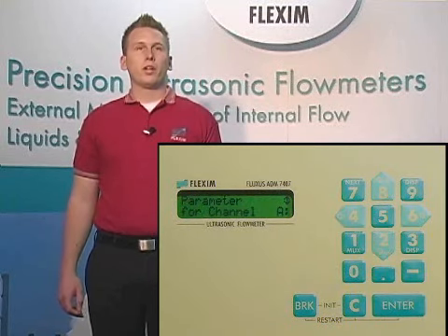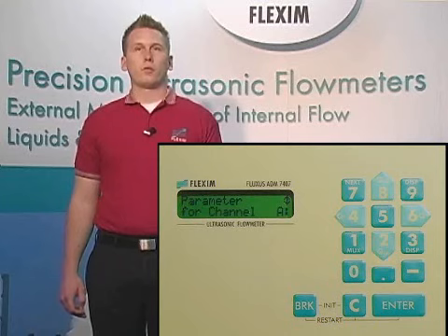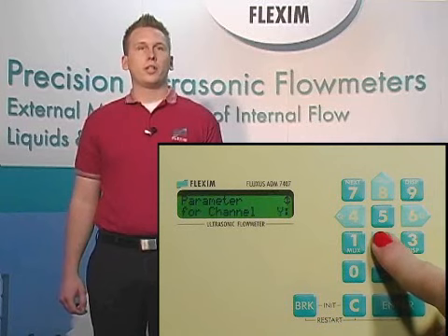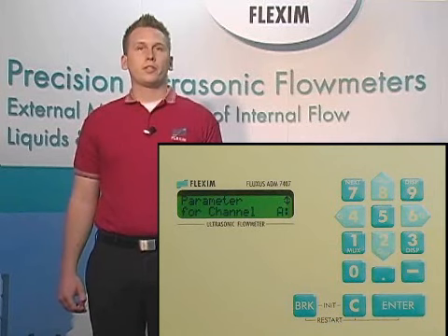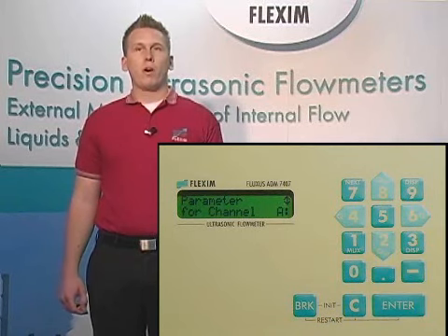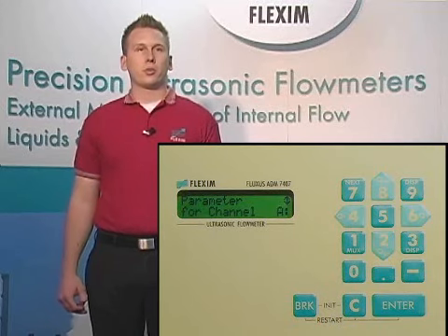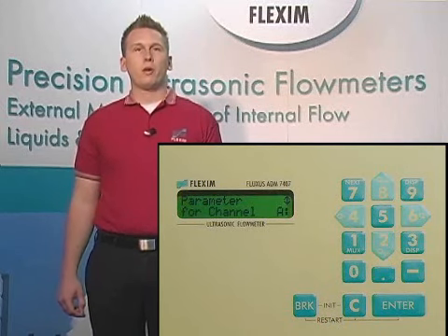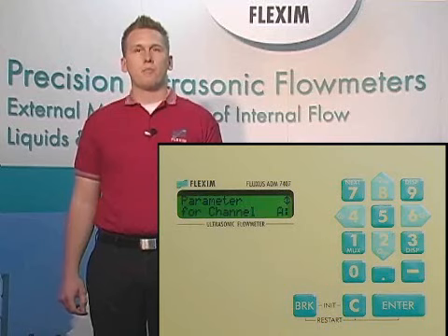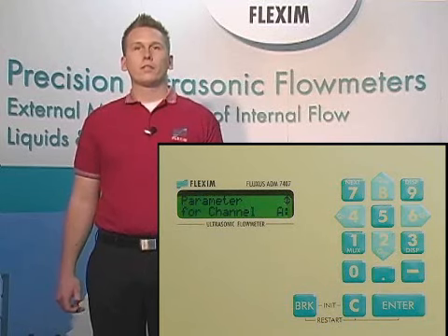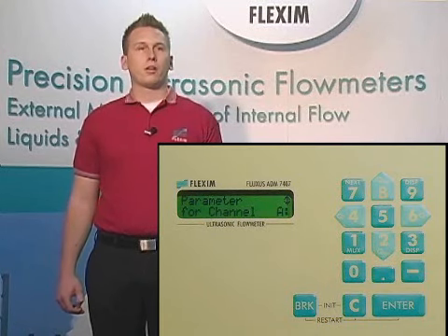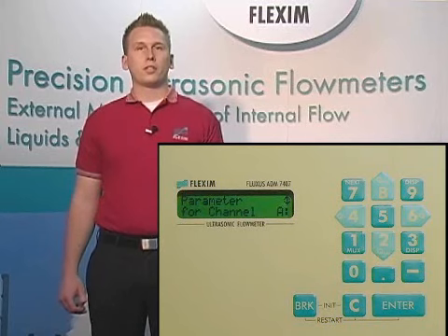Next, we can choose which channel to adjust parameters for if we're working with a 2-channel meter. We have options of setting channels A, B, Y, or Z. A and B are the physical channels in the meter, and channel Y and Z are calculated channels, so we can either average or sum the output from the physical channels A and B. For now, let's configure just the A channel, since most of you are probably interested in single channel measurement.